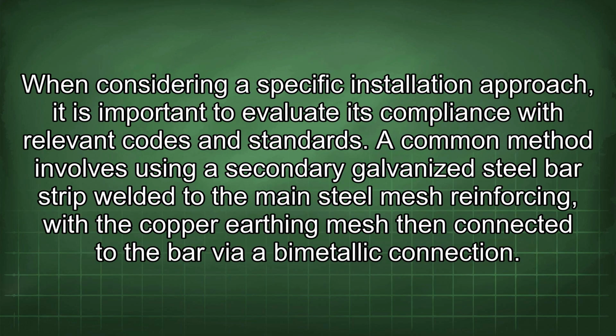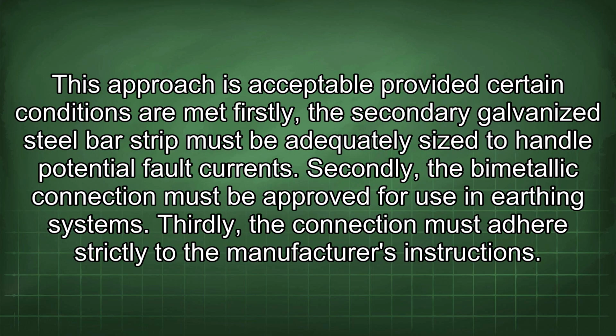When considering a specific installation approach, it is important to evaluate its compliance with relevant codes and standards. A common method involves using a secondary galvanized steel bar strip welded to the main steel mesh reinforcing, with the copper earthing mesh then connected to the bar via bimetallic connection. This approach is acceptable provided certain conditions are met.